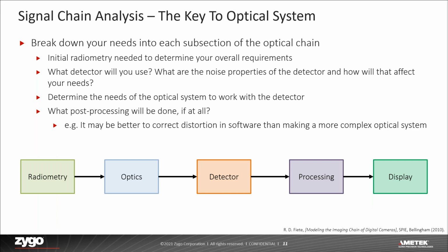Across all optical fields, one of the most important things to do upfront is go through your signal chain analysis. This process looks at the entire optical system to determine what requirements are needed for each subsystem of the device. In the case of imaging systems, you will first analyze the radiometric properties of the object or source and what output is needed from the device. You then may consider only the detector as a subsystem. The size of the detector and the pixel pitch drive the field of view and the resolution. Additionally, the noise from the detector may impact your final radiometric output. It's then important to choose the right detector. In the case of medical optics, the detector choice may be driven solely on the size of the detector and pixel pitch.